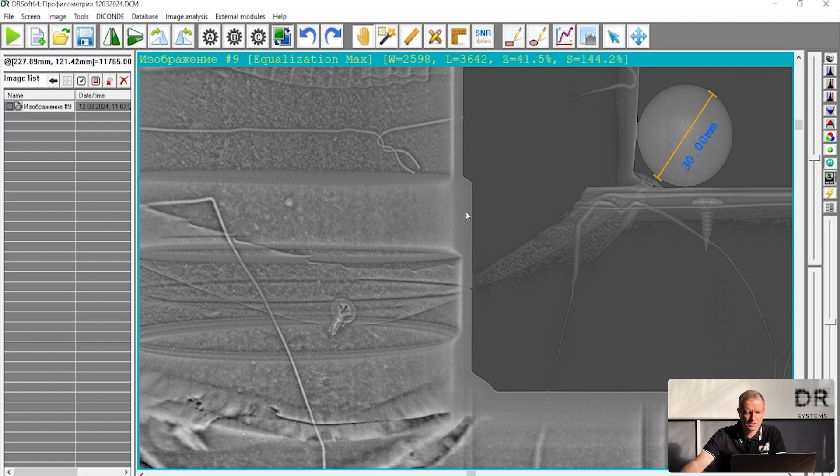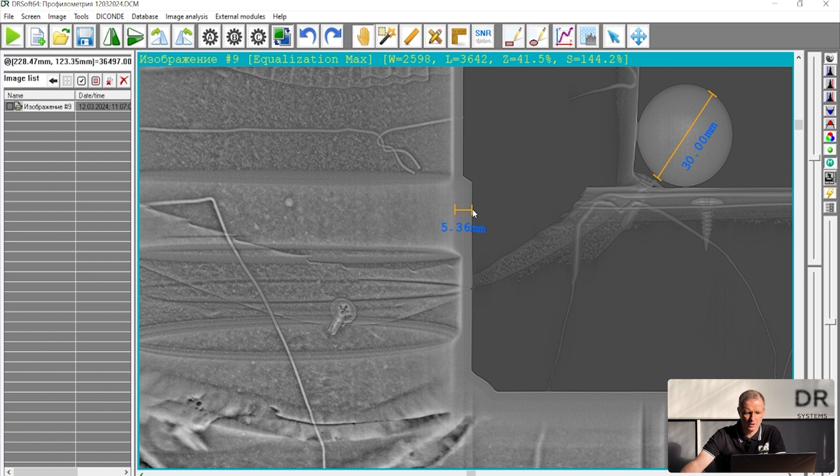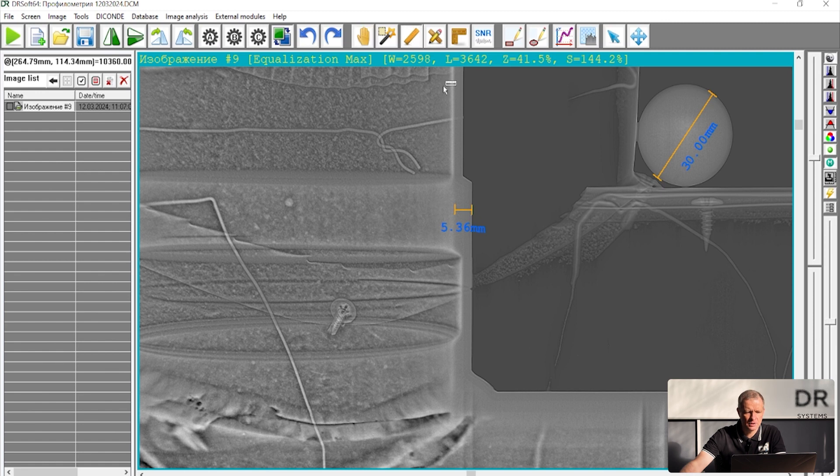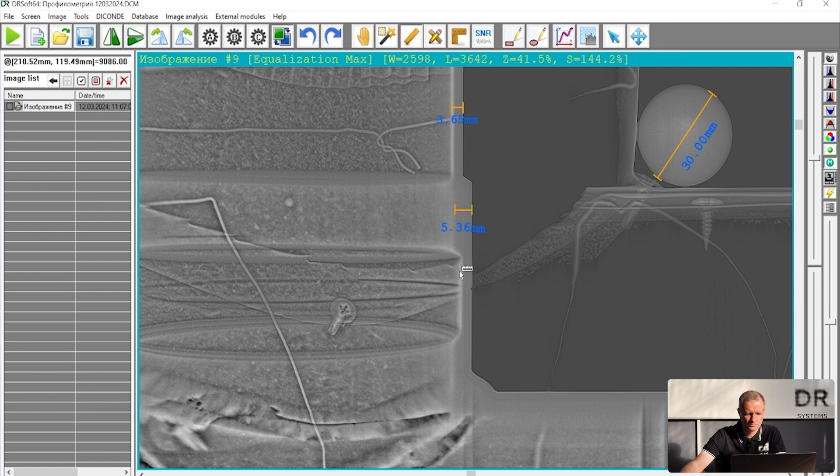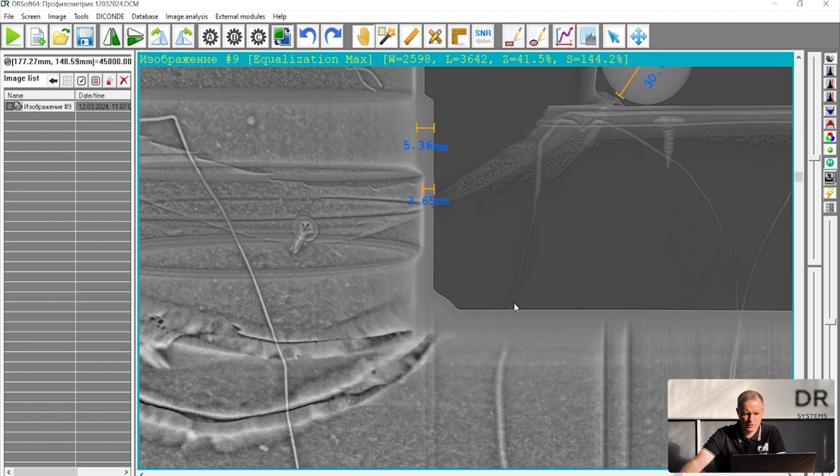I just put the ruler here and I try to find the inner and outer wall, outer border of the wall. So my estimation of the wall thickness for this place is 5.3 millimeter. Here it will be 3.6 millimeter. Here it's also 3.6. Probably it was the same sort of pipe. So let's look here.